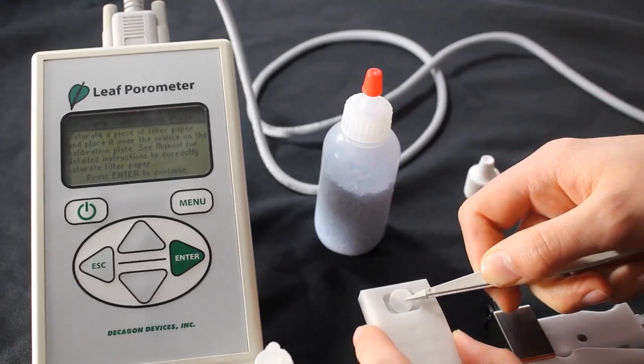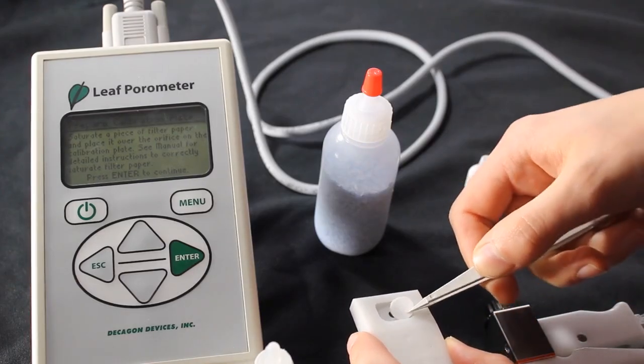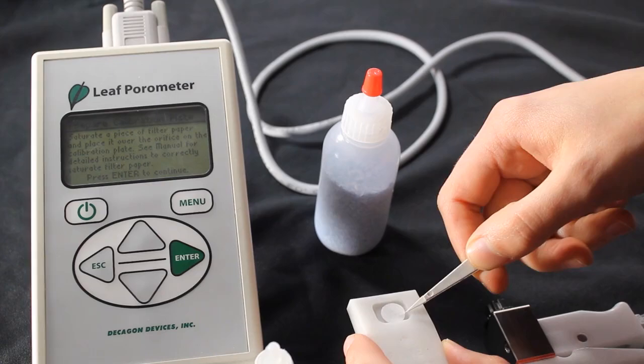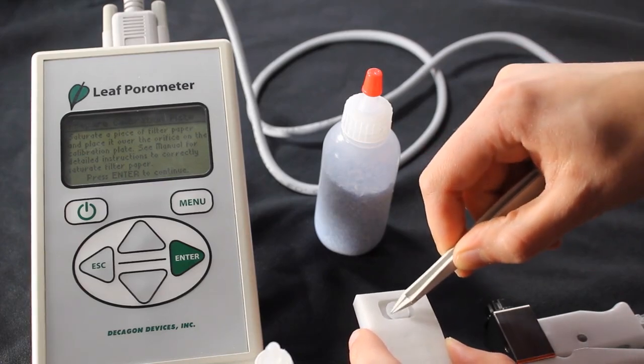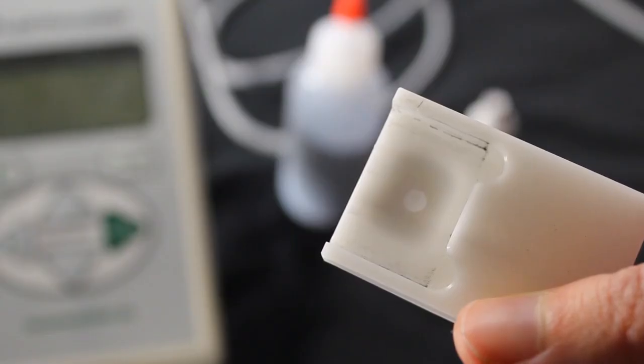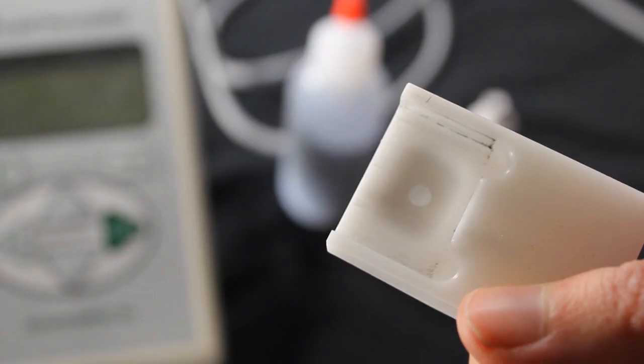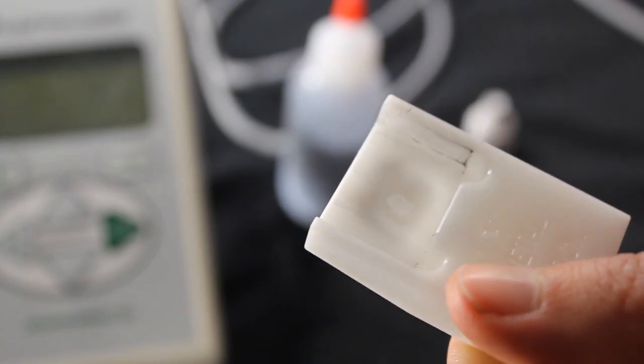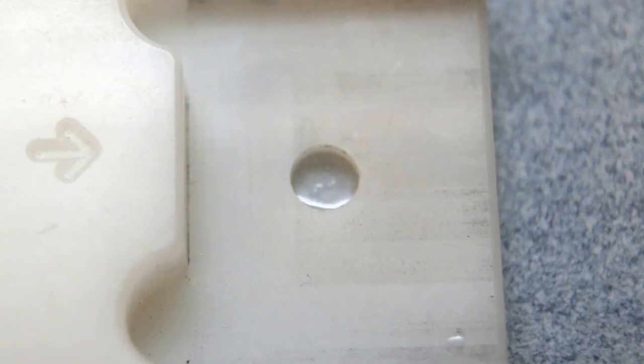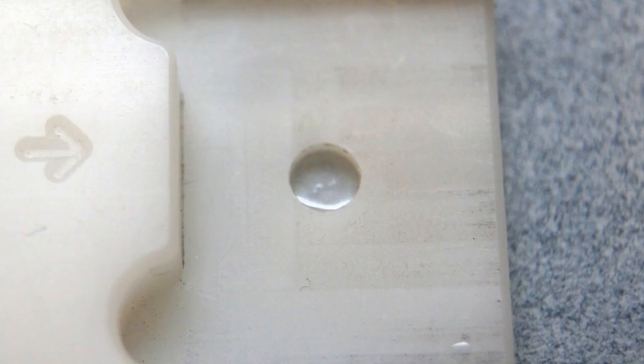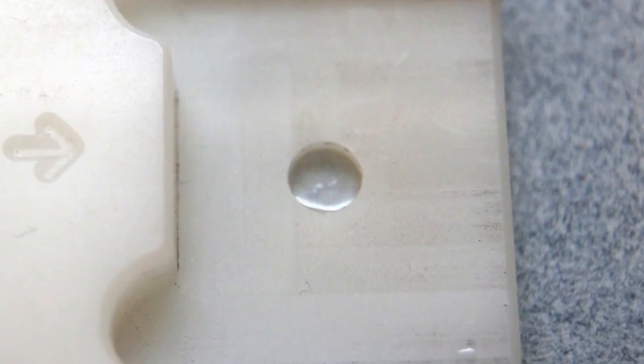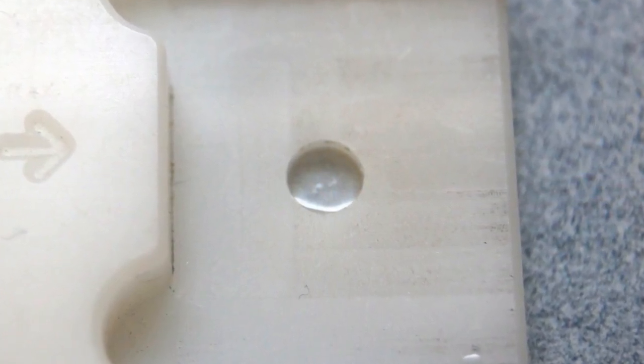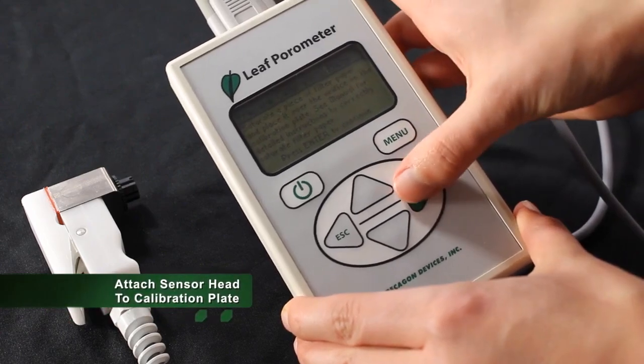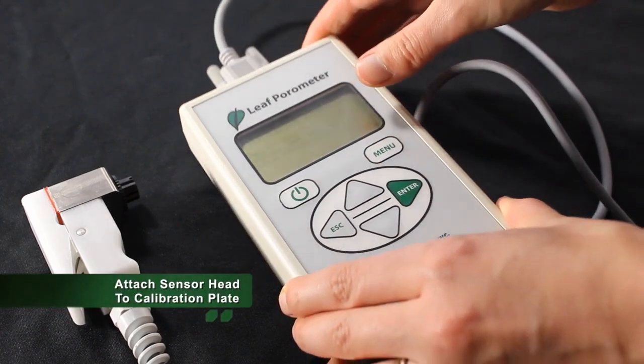After wetting the filter paper, lay it flat over the hole in the calibration plate on the side marked filter paper. Make sure the paper covers the entire hole and lays flat. Turn the calibration plate over and carefully examine the hole to make sure that no meniscus of excess water is present in the hole. If excess water is observed, remove the filter paper, dry the calibration plate, and repeat the wet and flick procedure with a more aggressive flick. With the moist filter paper in place, press Enter on the porometer control unit.